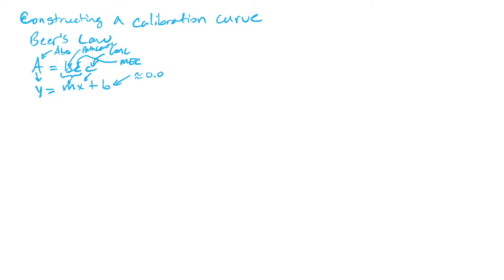What that means in real life is that whenever you take a blank and you put it into a spectrophotometer and you zero it out or blank the spectrophotometer, you're essentially telling the spectrophotometer that this should be zero because this is my standard sample that has no analyte in it. So no analyte should be zero. That's why in Beer's Law, the B for the Y-intercept in Y equals MX plus B isn't really represented.